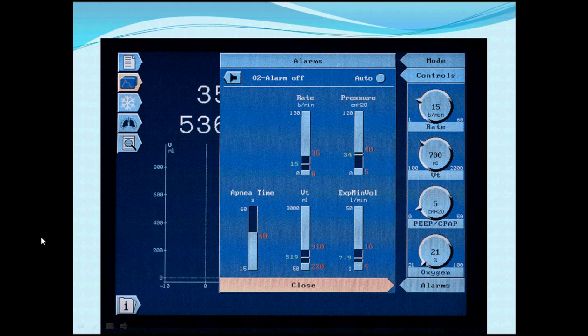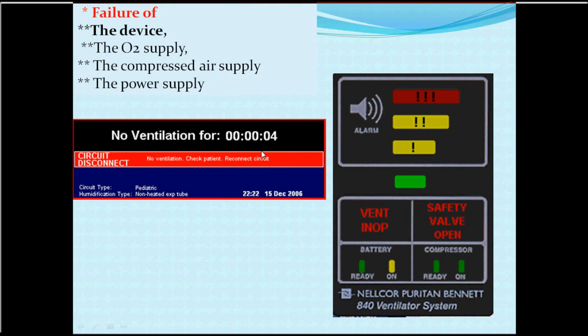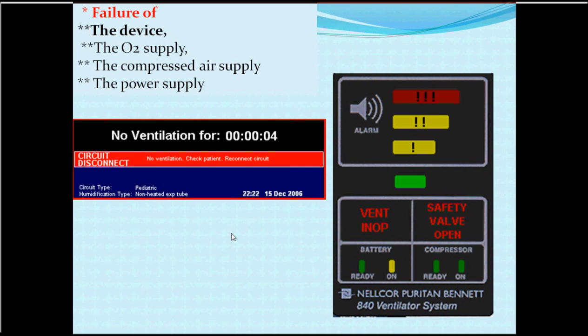Each ventilator has its own interface for setting alarm systems with high and low limits. There is also a device failure alarm — if something goes wrong with the device circuits, such as engineering problems, oxygen supply failure, air supply failure, or power supply issues, an alarm is triggered in yellow or red. A circuit disconnection will also generate an alarm. When an alarm sounds, always go look at the alarm value to understand what the problem is and handle it — never silence the alarm without investigating.